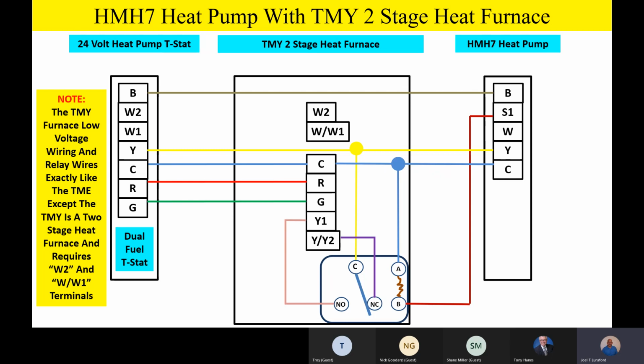Now, the only difference between a TMY and a TME furnace is the TMY is a 2-stage heating and 2-stage cooling capability. So we're going to keep the low voltage wiring exactly like we had it before. And please note the TMY furnace low voltage wiring and relay, it wires exactly like the TME. The only exception is the TMY is a 2-stage furnace and requires a W2 and a W/W1 terminal. So let's go ahead and hook those up for you real quick.